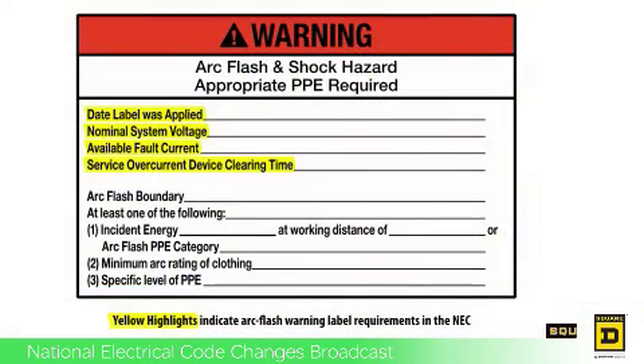equipment. There's also an exception to this section that allows you to omit this marking if you performed an arc flash hazard analysis in accordance with NFPA 70E, and that's evidenced by marking on the equipment. Now, this is a site-specific marking, so it depends upon the site-specific installation criteria and the overcurrent protective devices used. We have an example label here that would show you with the highlighted portions what the minimum requirements from this new change to the 2017 NEC.